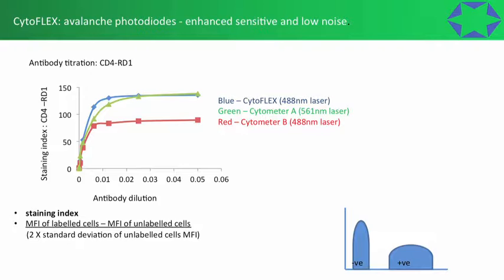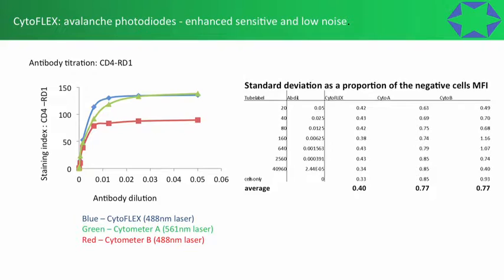Moving on to some more samples: this is an antibody titration with CD4 RD1, a PE-type antibody. We can see the staining index on the y-axis and antibody dilution on the x-axis across three different cytometers. The CytoFLEX shown in blue has a very good staining index comparable to cytometer A, which actually had a 561 laser. This surprised me because the CytoFLEX I was using had a 488 laser, so I wanted to look in more detail at how it managed to be so good.